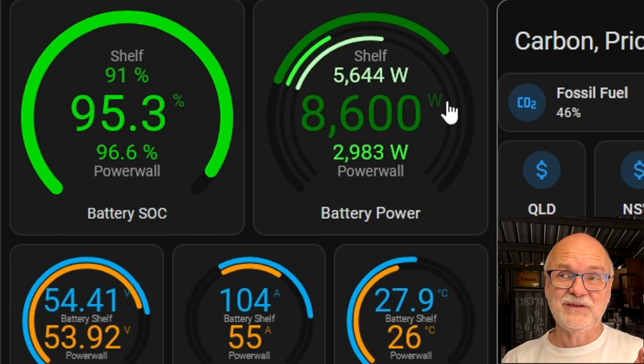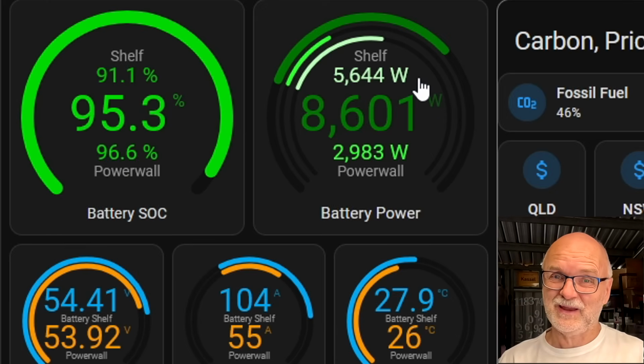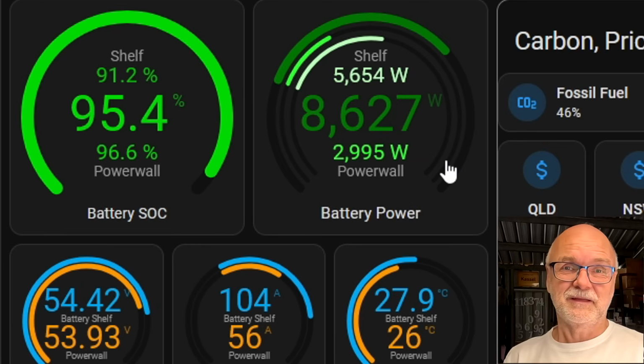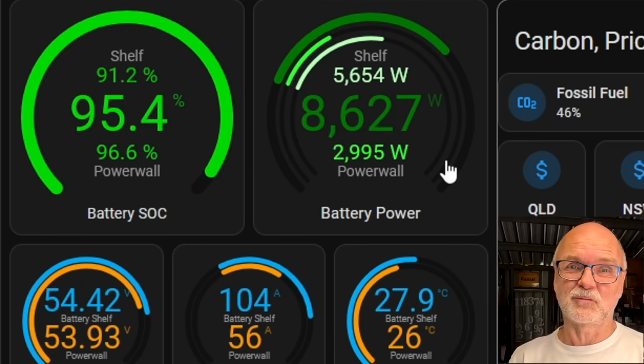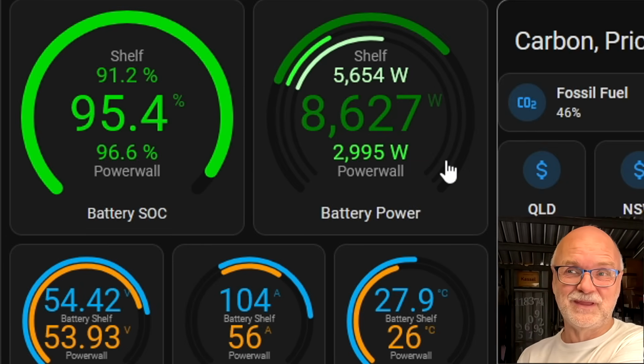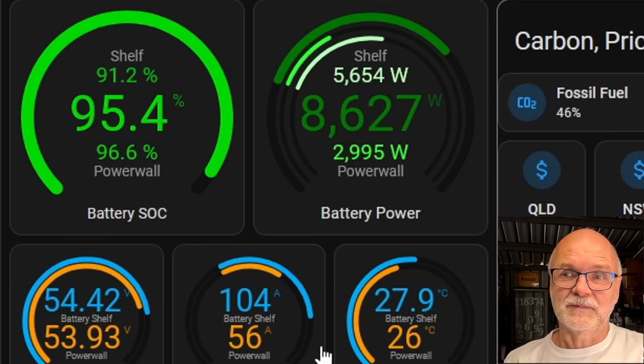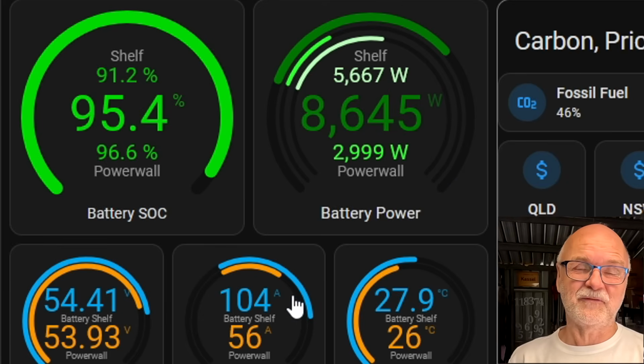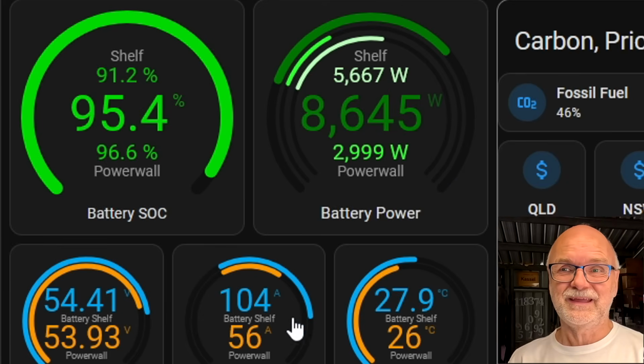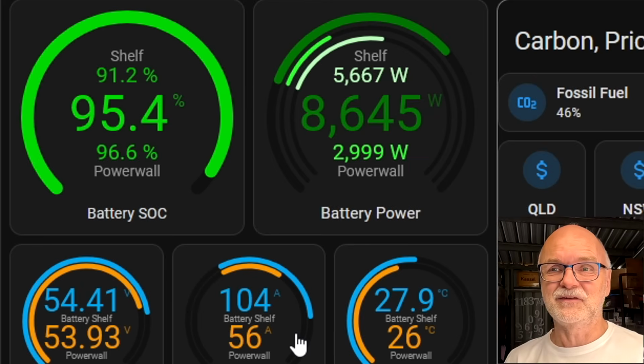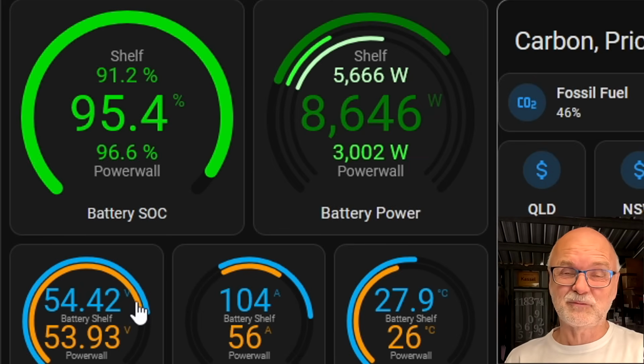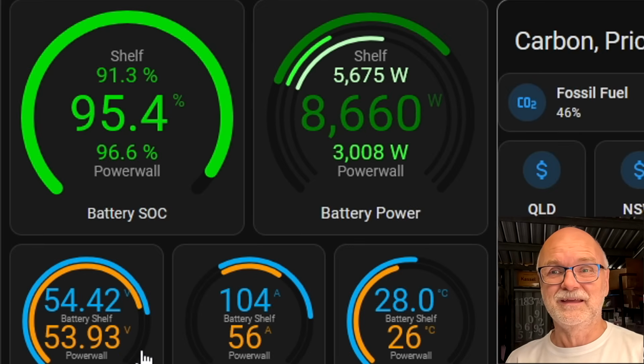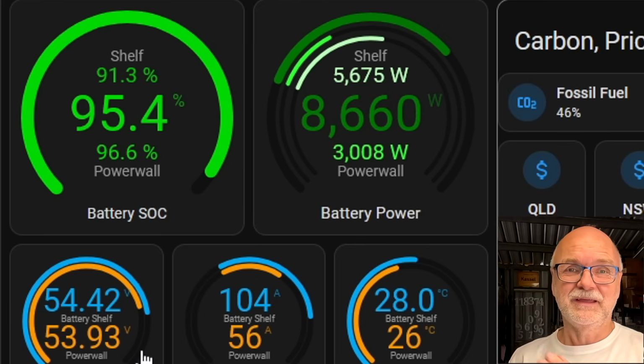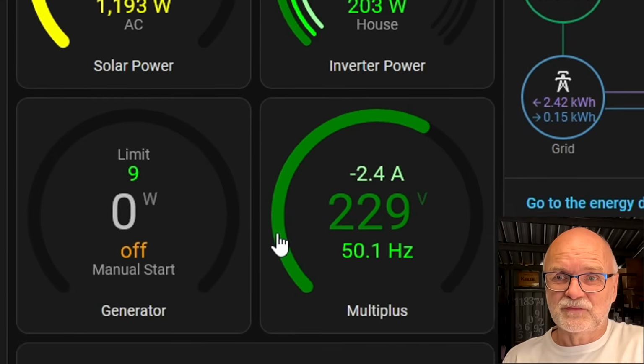Interestingly, 5.6 kilowatts going into the battery shelf with only 3 batteries, and close to 3 kilowatts going into the remaining 10 batteries on the other side in the Powerwall. This corresponds to 104 amps into the battery shelf and only 56 amps into the Powerwall. Battery charge voltage is 54.4 volts in the battery shelf and only 53.9, half a volt lower, in the Powerwall. I want to show you something else here.